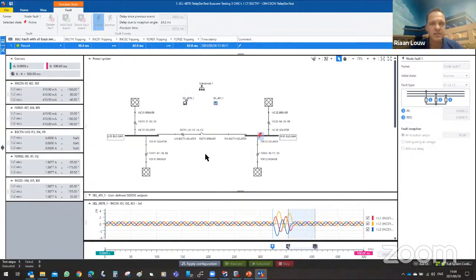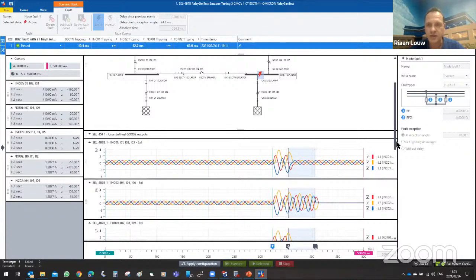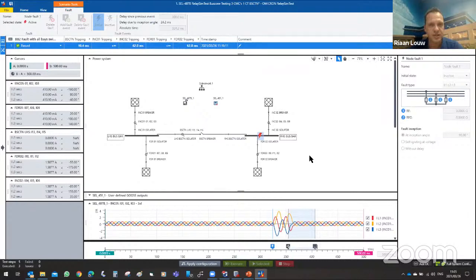At that instance, it will recognize why current flows in incomer 1 and feeder 1, because it recognizes that this is still balanced, but if I go down here, incomer 2 and feeder 2 is not. Then it makes a new decision to say, okay, this definitely is a zone 2 fault, so I can then isolate zone 2 accurately.